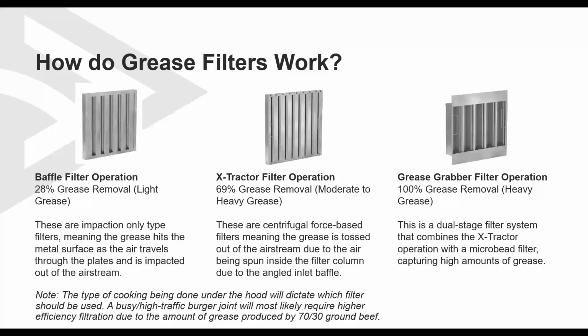And lastly, we have the grease grabber filter option. This is 100% efficient at grease removal, and you would use this in a heavy-duty grease application. This is a dual stage filter system that combines the X-Tractor that I previously mentioned with a micro bead filter. This captures high amounts of grease.